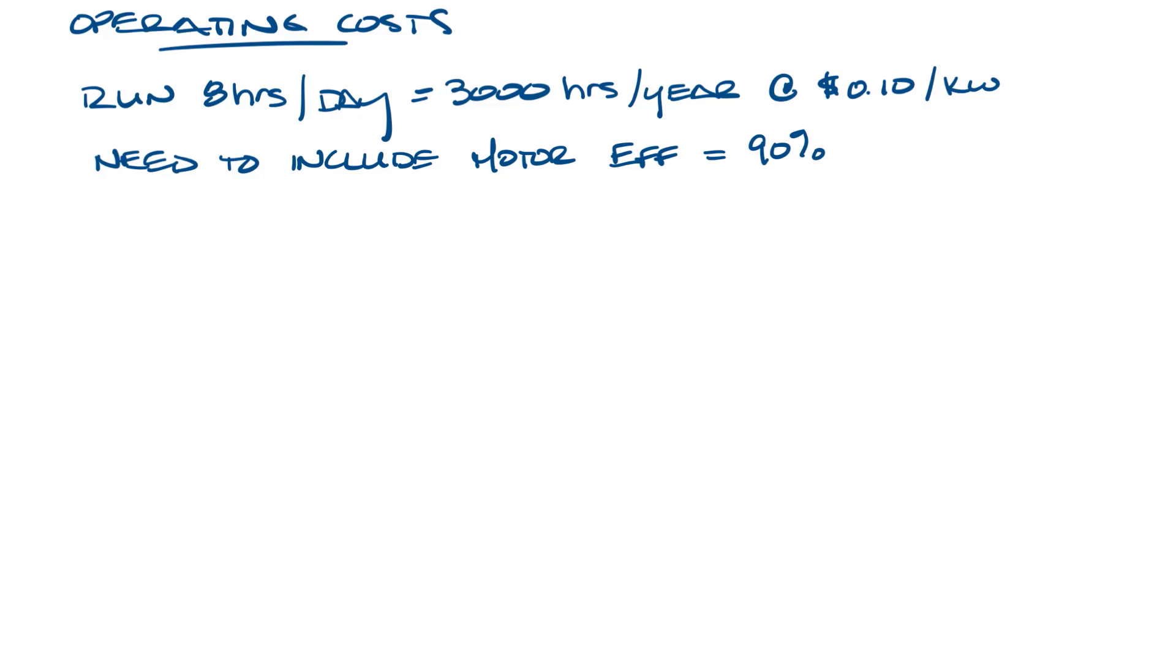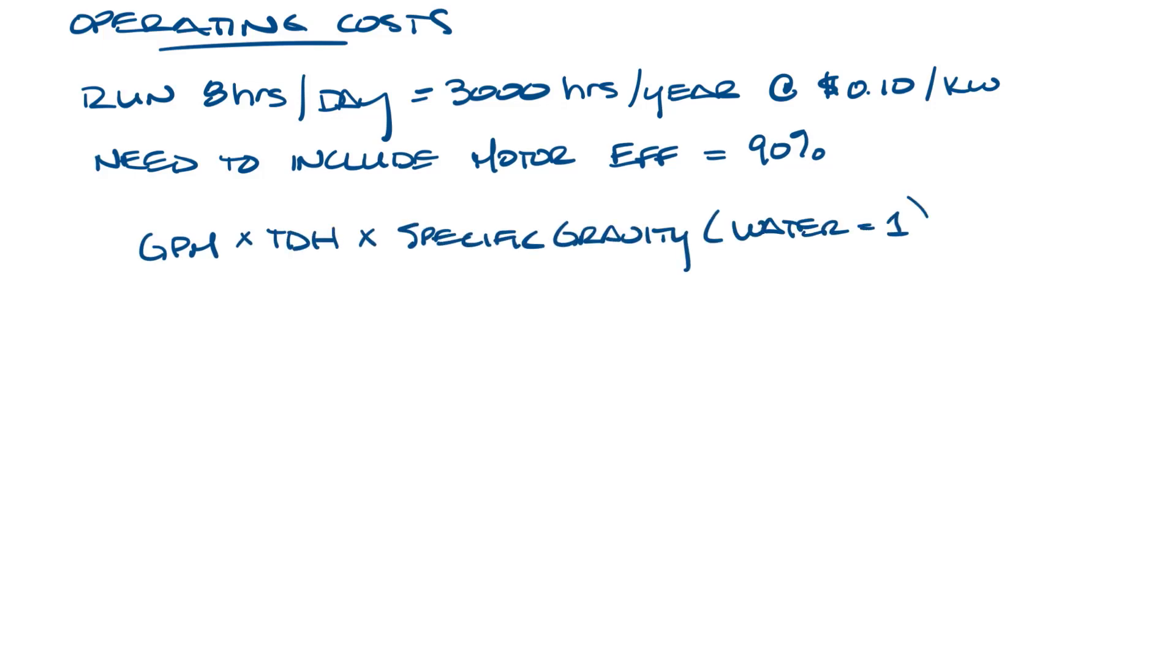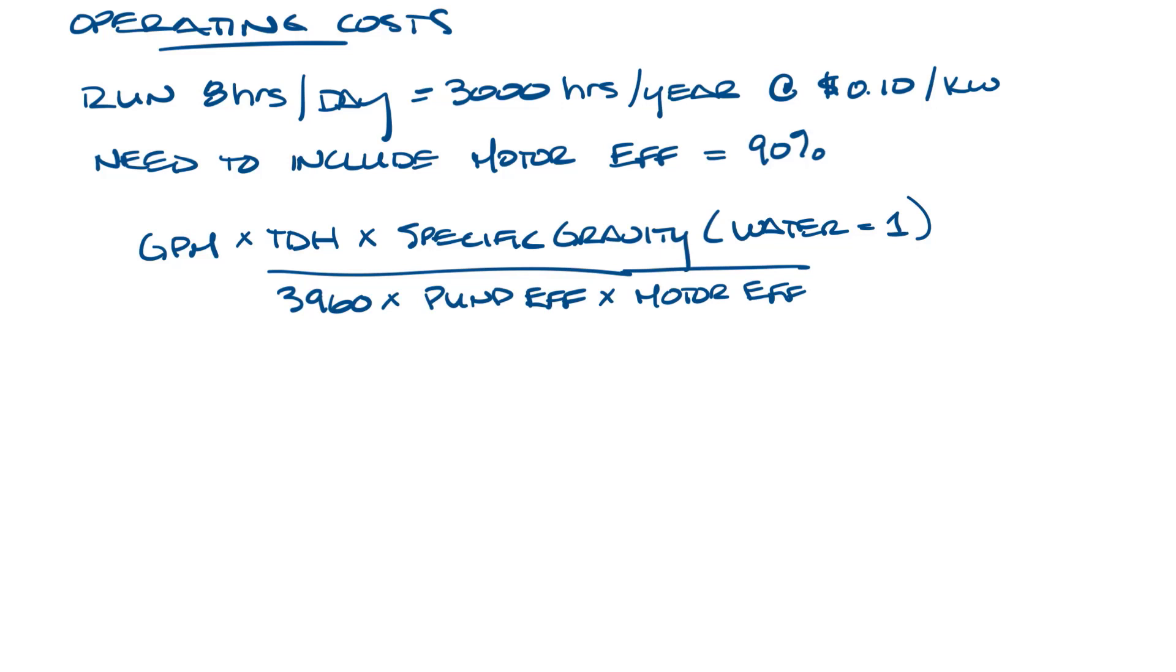The equation to calculate the electrical horsepower of a pump is GPM times TDH times the specific gravity, which we're just going to use one for water, divided by 3960 times the pump efficiency times the motor efficiency, and then we'll multiply all of that by 0.746 to convert to kilowatt.